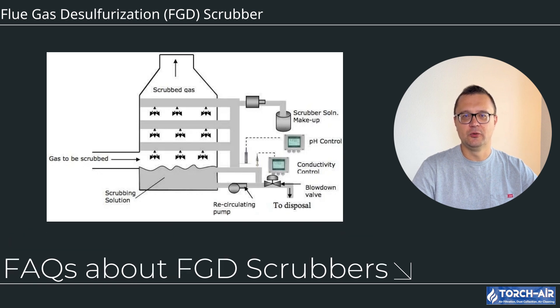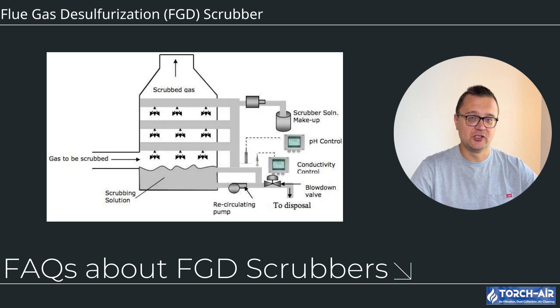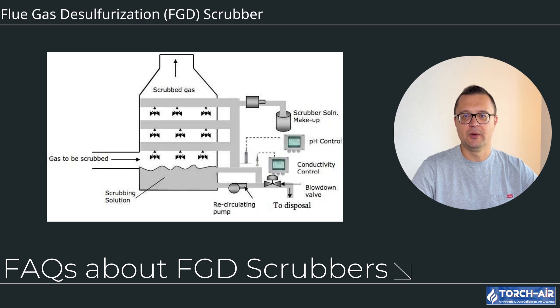FAQs about FGD scrubbers: What is the main difference between wet and dry FGD scrubbers? Wet scrubbers use a liquid to capture and neutralize SO2, whereas dry scrubbers use a solid sorbent. Wet scrubbers generally have higher efficiency, but dry scrubbers are more suited for water-constrained environments. Can FGD scrubbers be used in cold environments? Yes — FGD scrubbers can be designed with heating systems to prevent freezing of the scrubbing liquid, particularly in wet systems. What are the by-products of wet FGD systems? The primary by-product is gypsum (CaSO4·2H2O), which can be used in construction materials like wallboard.